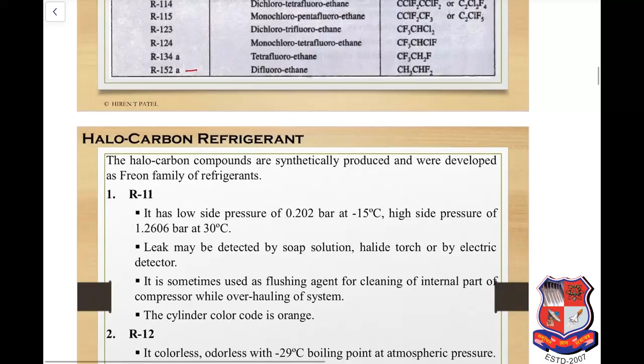So the first refrigerant, that is R11. It has a low side pressure of 0.2 bar at minus 15 degree Celsius and a high side pressure of 1.26 bar at 30 degree Celsius temperature. Leak may be detected by soap solution, halide torch or by electric detector. It is sometimes used as a flushing agent for cleaning the internal parts of the compressor while overhauling the system. This refrigerant is stored in an orange color cylinder. So the cylinder color code is orange for R11.